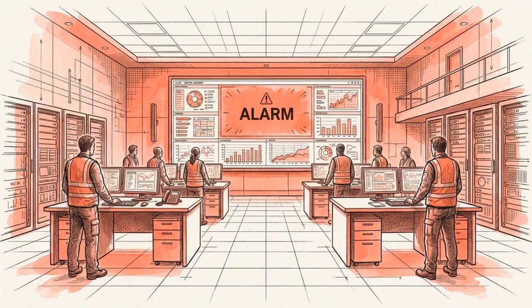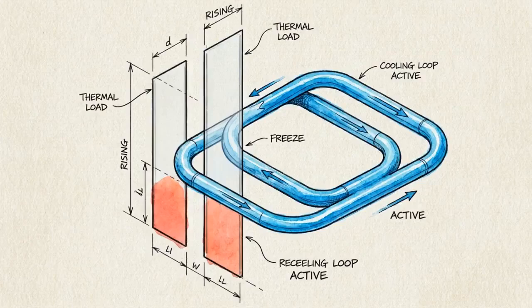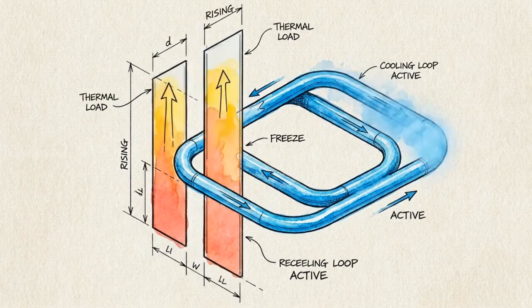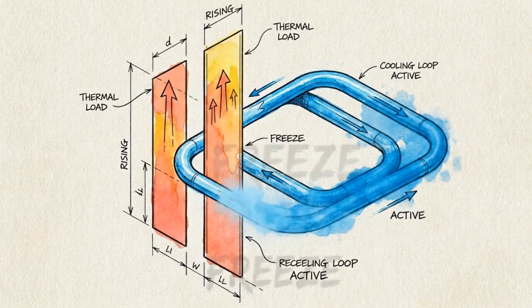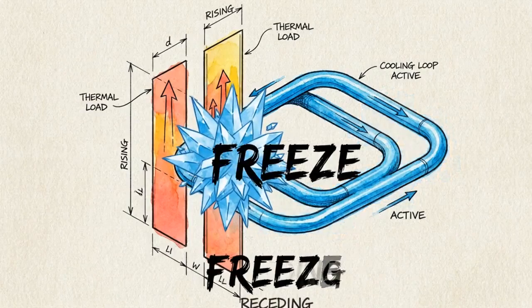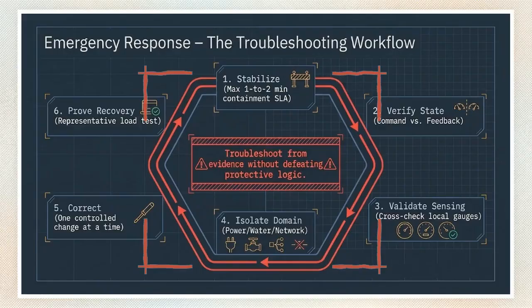When critical faults bypass predictive maintenance, operators work under a strict 1 to 2 minute containment SLA. The immediate priority is not diagnosing the broken component, it is intercepting the rising thermal load and stabilizing the service. This hexagonal diagram maps the 6-step troubleshooting workflow used to systematically contain and correct a fault without inducing secondary errors. Step 1 dictates starting thermal energy storage or alternate standby paths first.